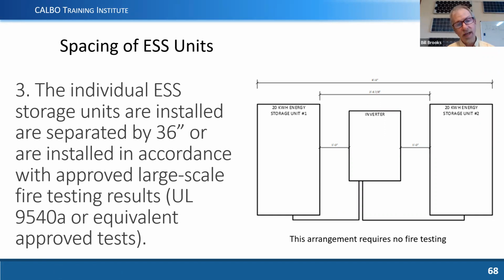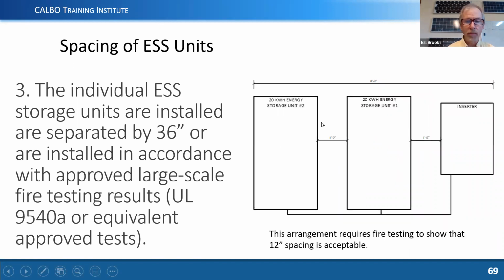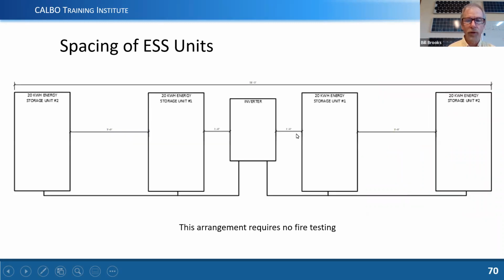By the way, almost every single manufacturer of an ESS wants to do these UL 9540A tests. If you're doing 2 units, one on either side of the inverter, it's actually really easy, because the inverter needs spacing between other equipment, and it's pretty easy to get that 3 feet without any large-scale fire testing. However, if you wanted to put them both on one side, having an extra 3 feet of room can be a real pain in the butt. Here's an example: if I wanted to go to the full 80 kilowatt hours allowed in the code in my attached garage, and I had a 3-foot requirement, this is how I'd have to install it. It would take fully 18 feet of wall space.